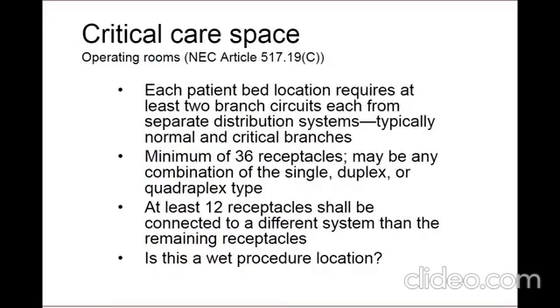An operating room is a critical care space with additional requirements on top of other critical care spaces. There must be at least 36 receptacles in any combination of single, duplex, or quadruplex type. At least 12 of the 36 receptacles must be connected to either the normal branch circuits or critical branch circuits supplied from a separate ATS than the one supplying the remaining receptacles that are connected to the main critical branch circuits in the operating room.